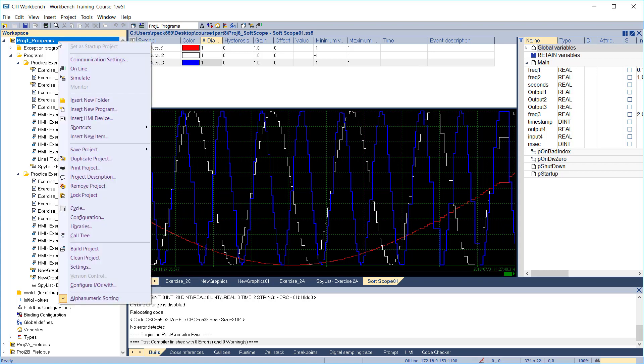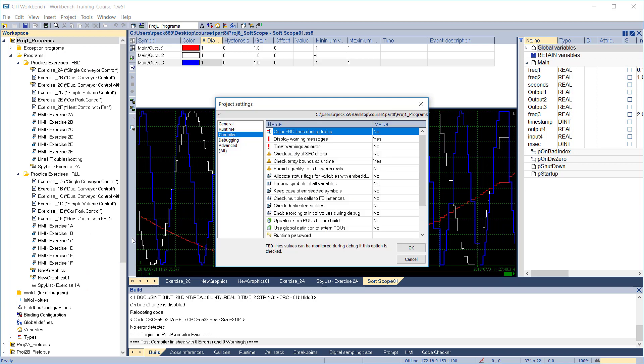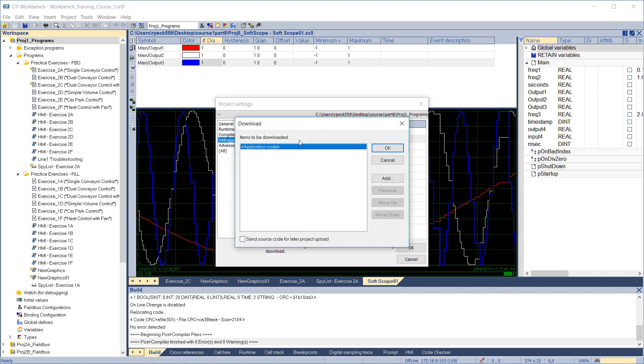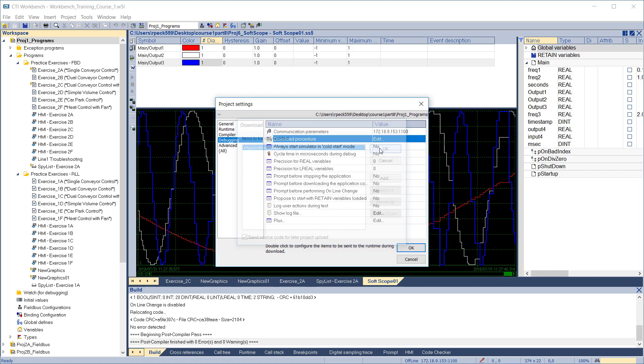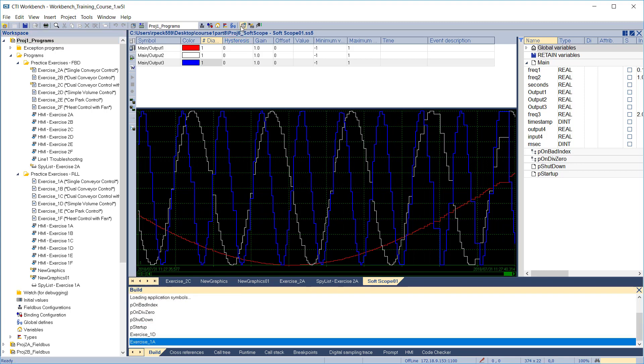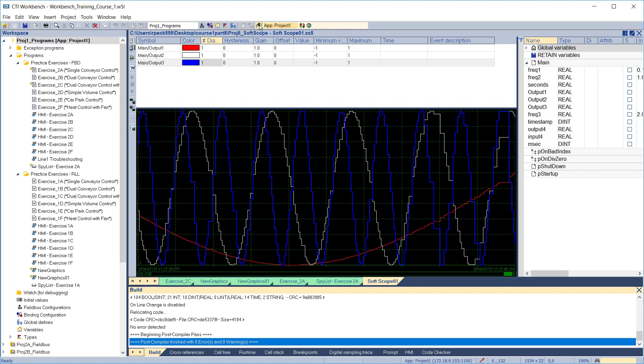Automatic downloading can be configured in project settings. Right-click on the project name and select settings. Under the debugging category, edit the download procedure item. Click the box at the bottom to send source code. Now each time the project is downloaded, a set of source files for the project will be stored on the SD card on the target device.